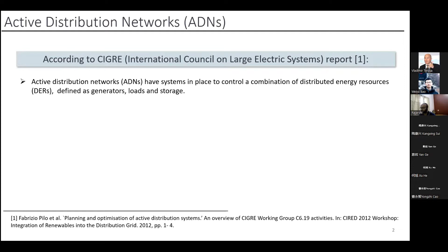Let's first define what is an active distribution network. According to a CIGRE working group committee report, an active distribution network is a network which has a combination of distributed energy resources such as solar PV generators and other DERs, and also controllable loads and storage integrated into the system. The distribution system operator in such a scenario has the possibility of managing the electrical power flow in the network using various schemes such as flexible network topology, or using devices such as STATCOMs, to change the power flow in the network to suit the voltage profile of the network.